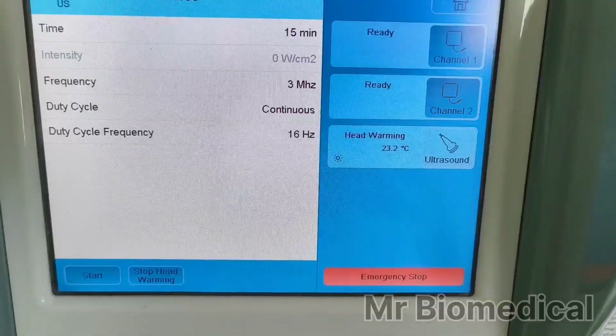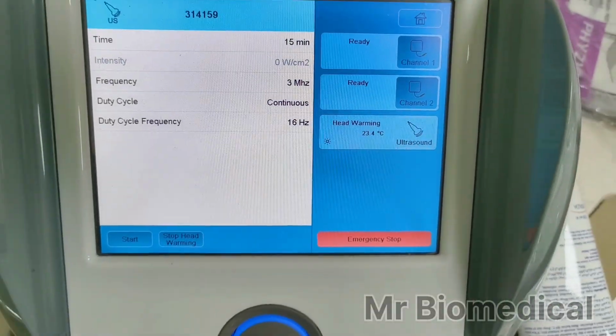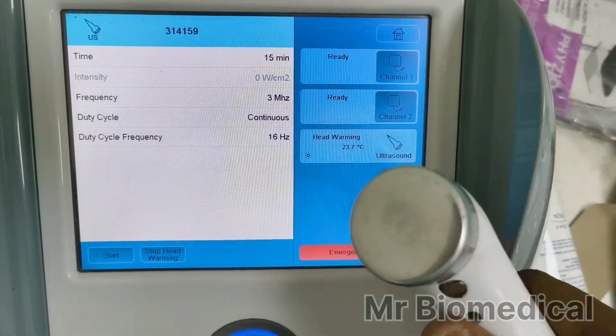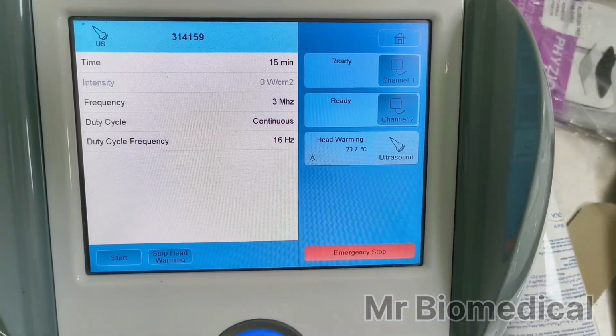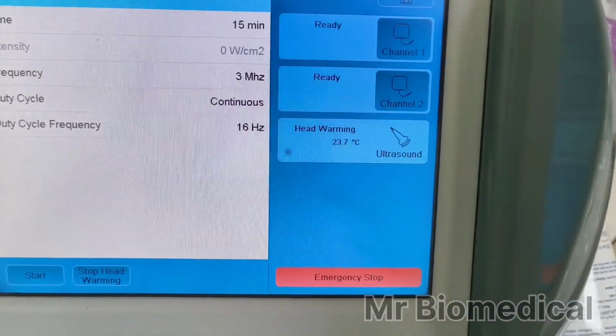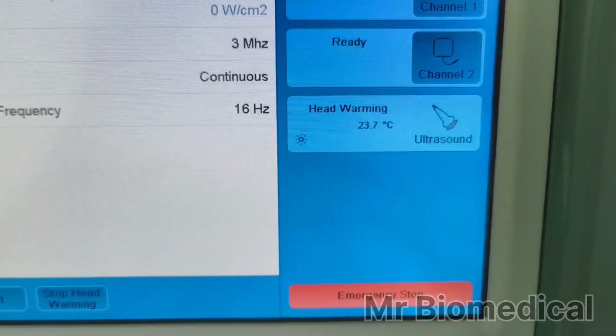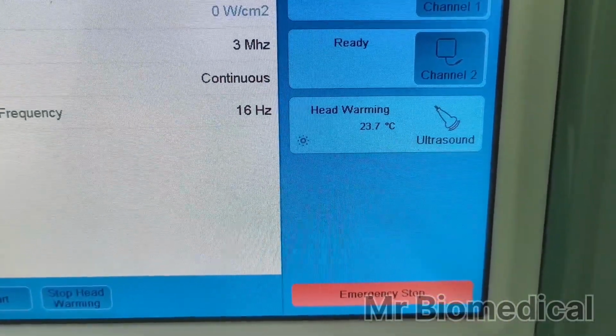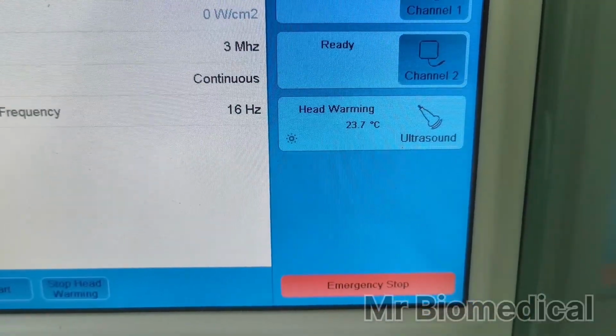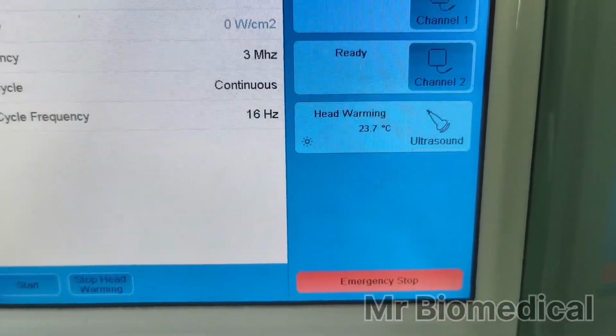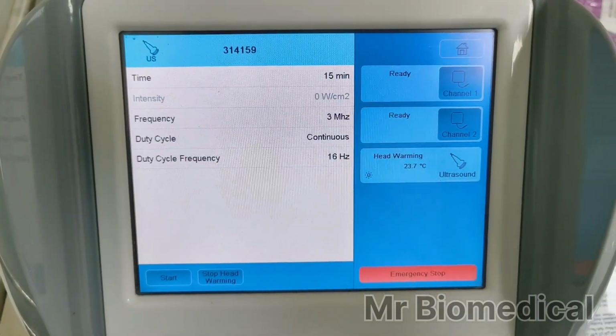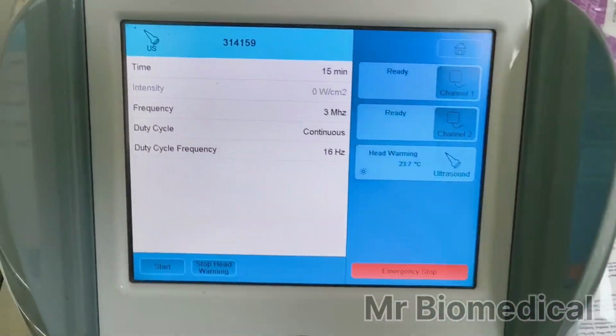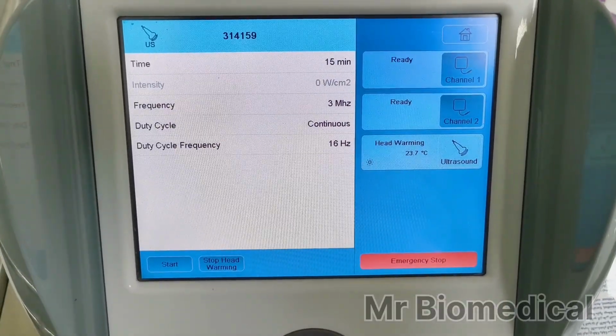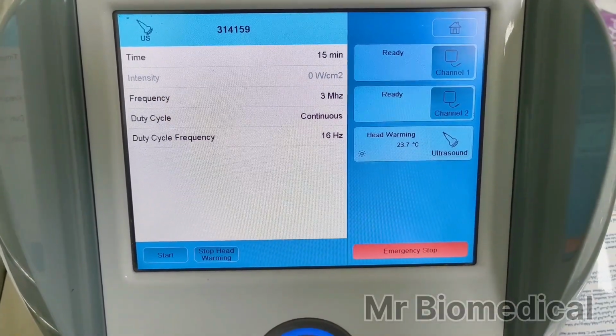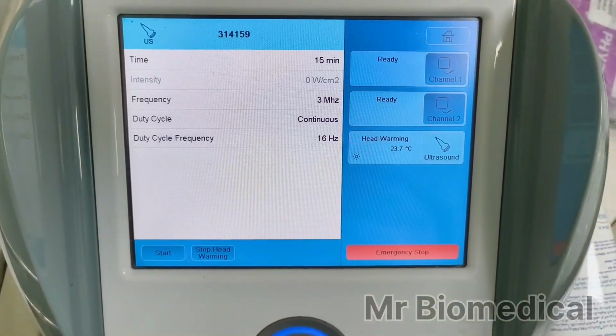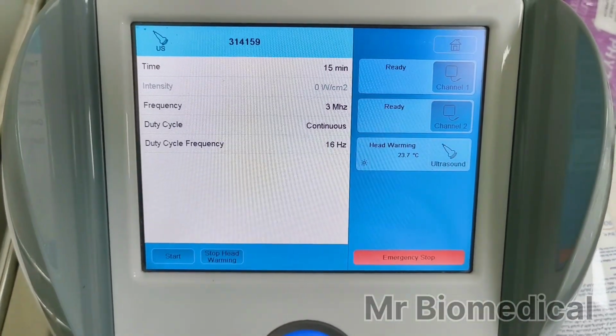But if it is not working after putting the 314159 code, then you can assume that the probe is the issue. You have to change the probe. But now here you can see the head is warming up. And there is no error message coming, so the machine is working good. No need to change the probe. But if it is not working, you have to change the probe.